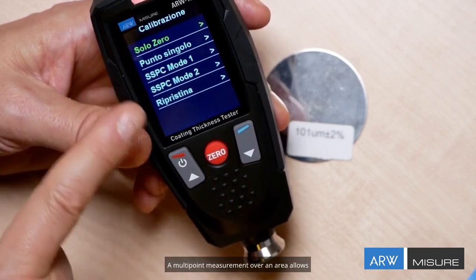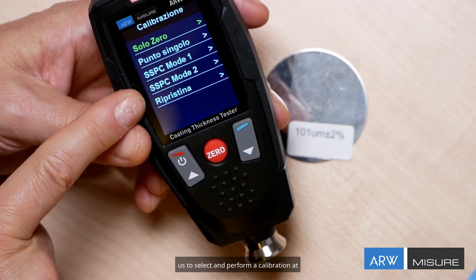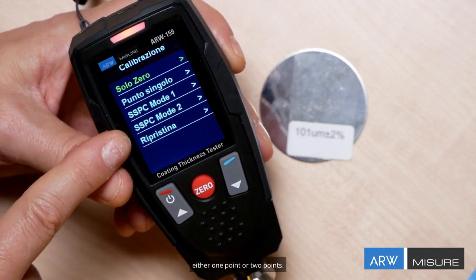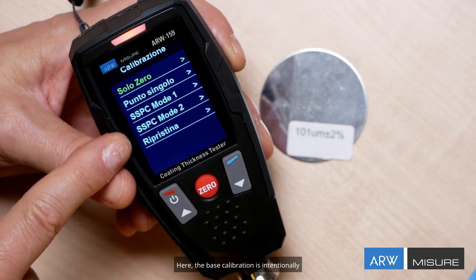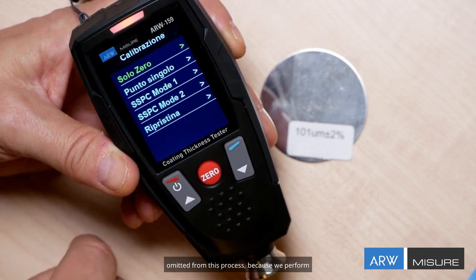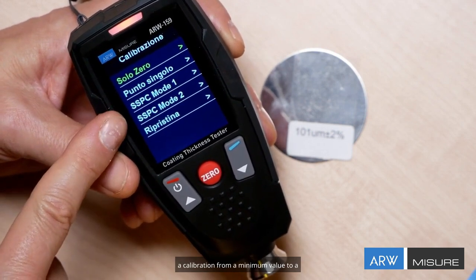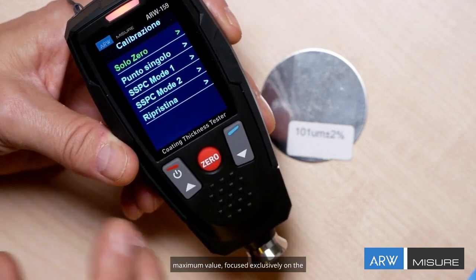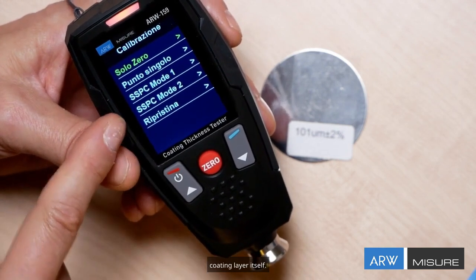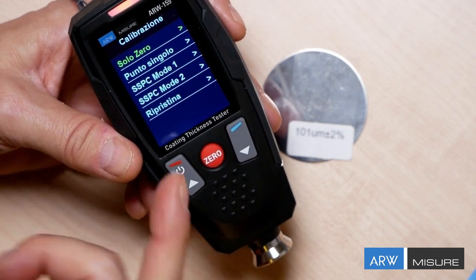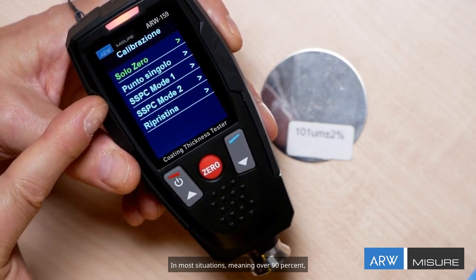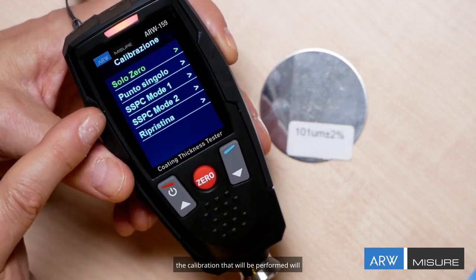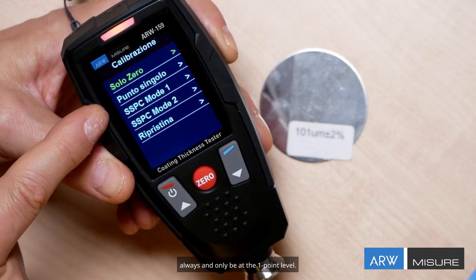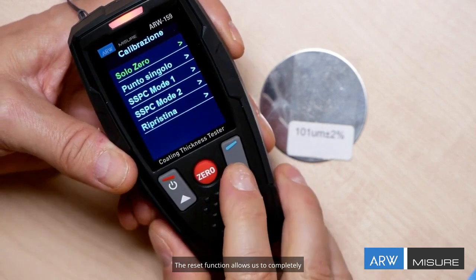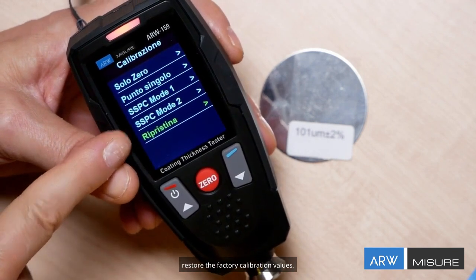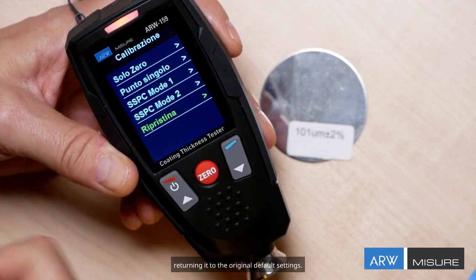A multi-point measurement over an area allows us to select and perform a calibration at either 1 point or 2 points. Here, the base calibration is intentionally omitted from this process, because we perform a calibration from a minimum value to a maximum value, focused exclusively on the coating layer itself. In most situations, meaning over 90%, the calibration that will be performed will always and only be at the single point level. The reset function allows us to completely restore the factory calibration values, returning it to the original default settings.